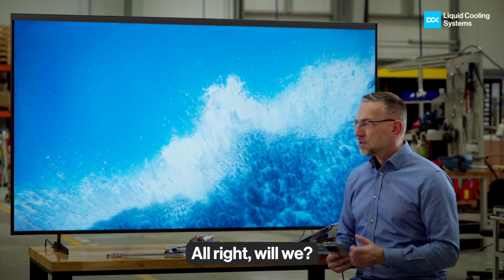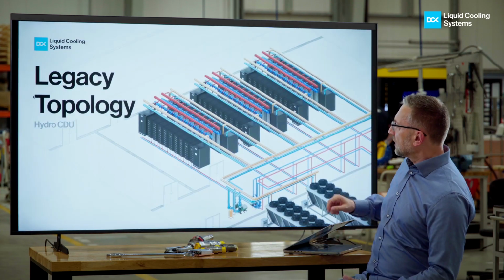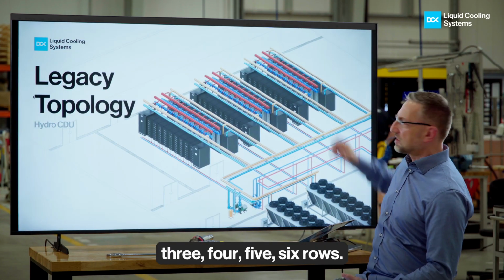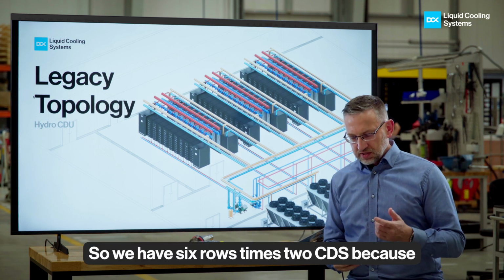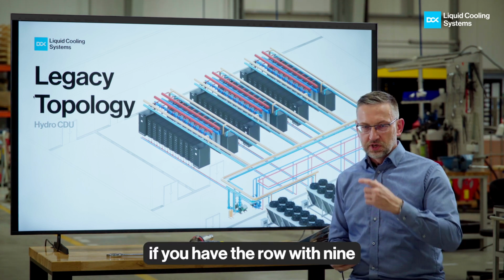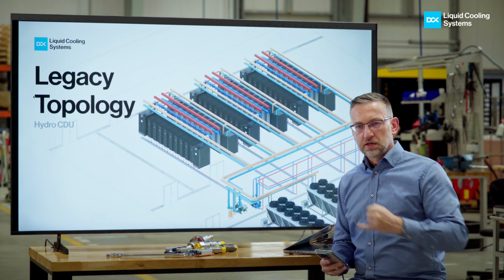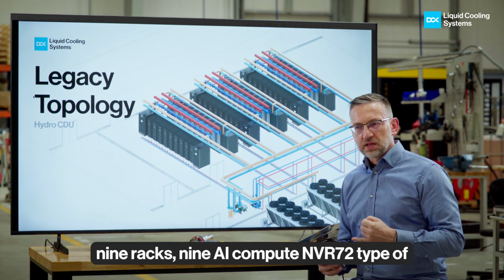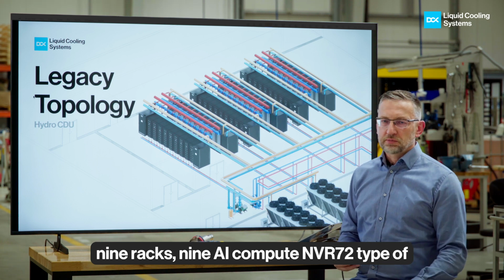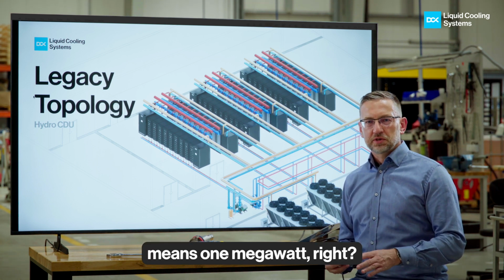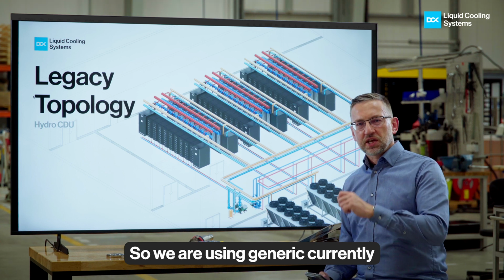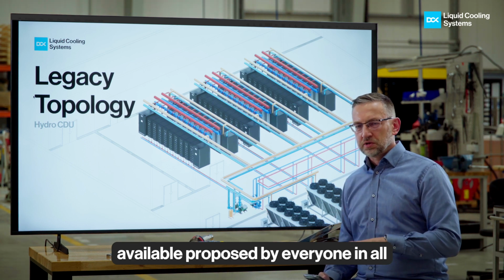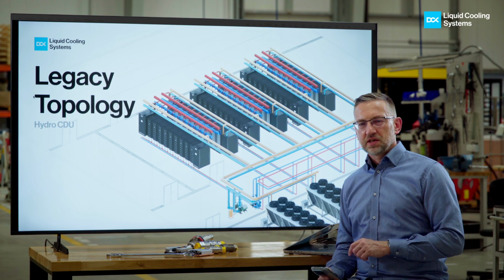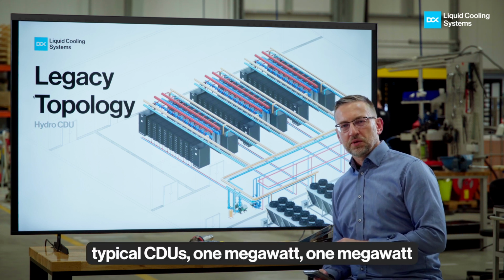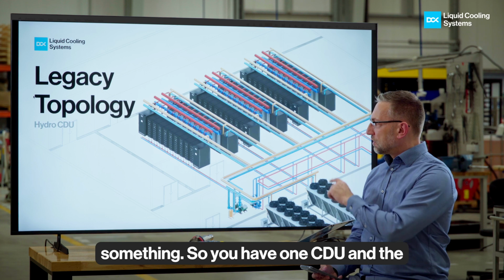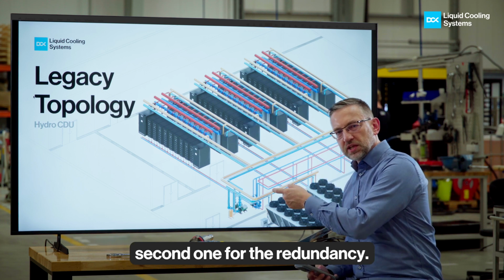Let's do the quick math, all right? Let's say we have 1, 2, 3, 4, 5, 6 rows. So we have 6 rows times 2 CDUs, because if you have a row with 9 racks, 9 AI compute NVL72 type of racks, well, that means 1 megawatt. Right, so we're using generic, currently available, typical CDUs proposed by everyone in all those topologies and reference designs, 1 megawatt something. So you have 1 CDU and the second one for the redundancy.